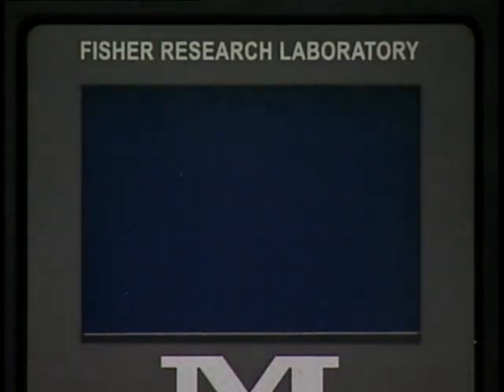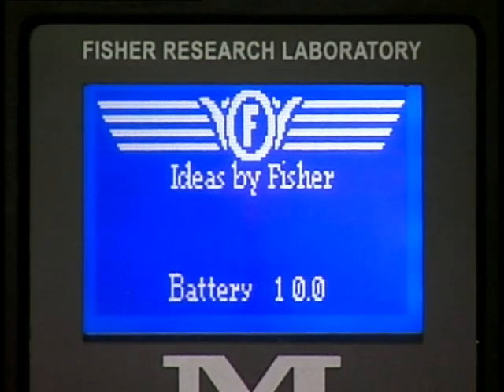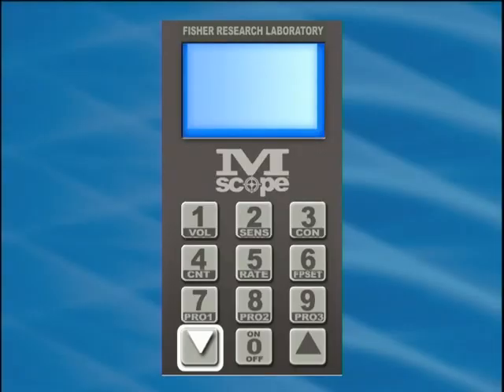To enter the diagnostic mode, begin with the power to the M-Scope turned off. Turn the power on and quickly press the down arrow key and then the up arrow key. Then wait for the unit to complete its LED sequencing self-test pattern. Each of these arrow key presses must be done within two seconds of powering on.